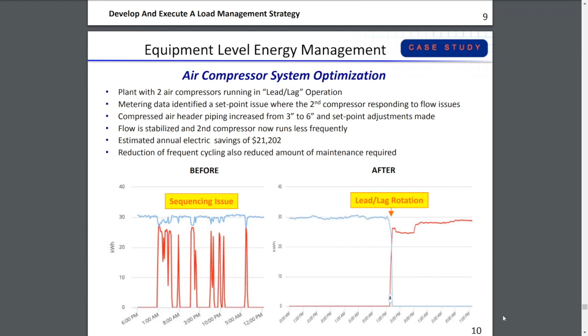Okay. Another example, air compressors are a pretty standard load for us to work with. This was a case where we had been asked to put metering on air compressors to help develop operational costs. They just wanted to know how many kilowatt hours were consumed over the month and what it cost them to run the units. But something else that came out of the data was on the graph on the left, there are two lines, a blue and a red, for two different compressors. One of the units was running fairly normally as a baseline. The other unit was coming on very randomly once in a while just to make up for small gaps in pressure required. And when we see something like that, it's a sign that the second unit is coming on, but it's just on the verge of not being needed.